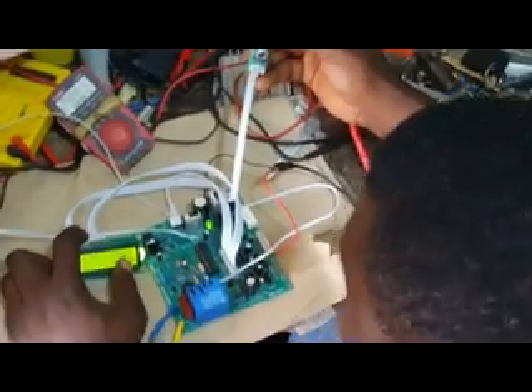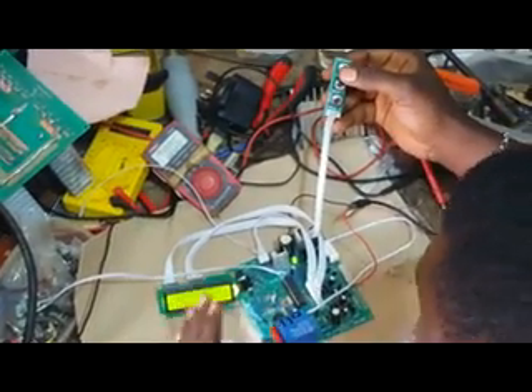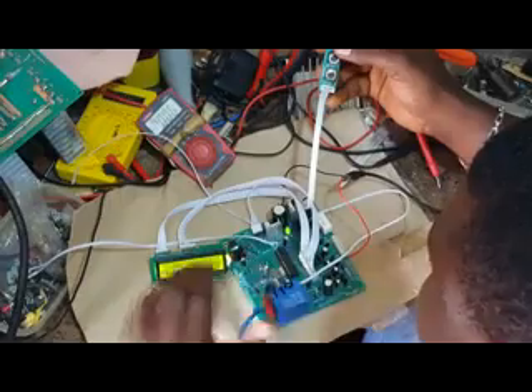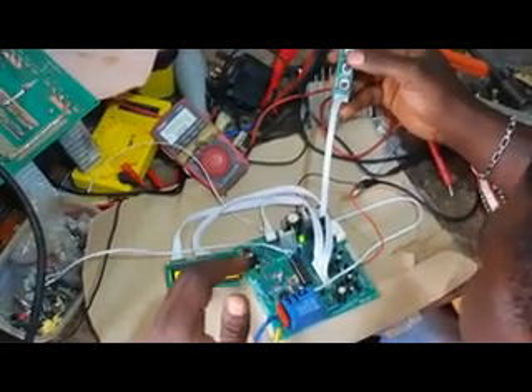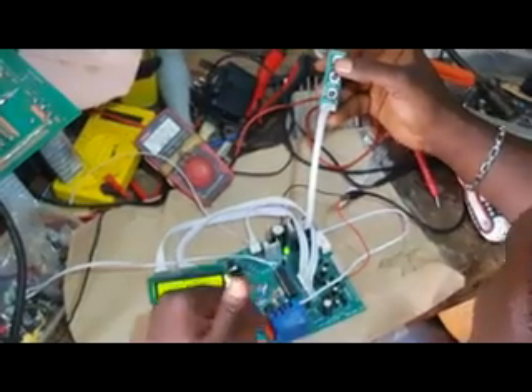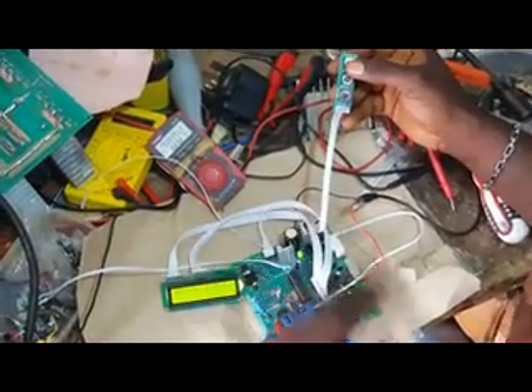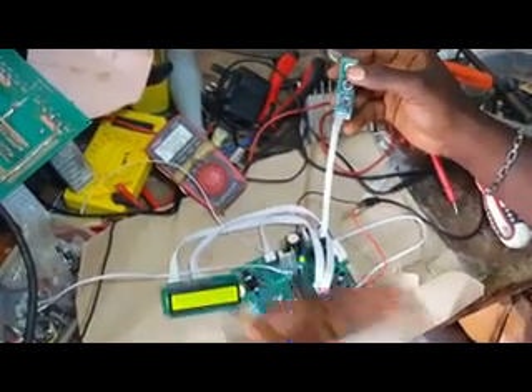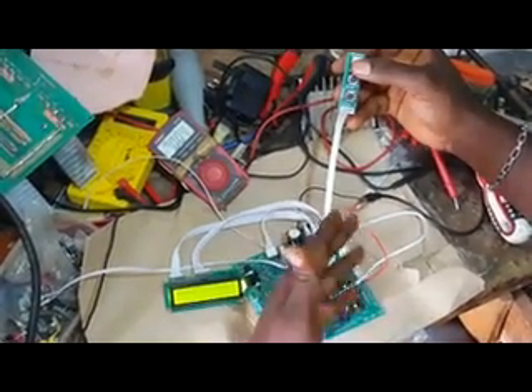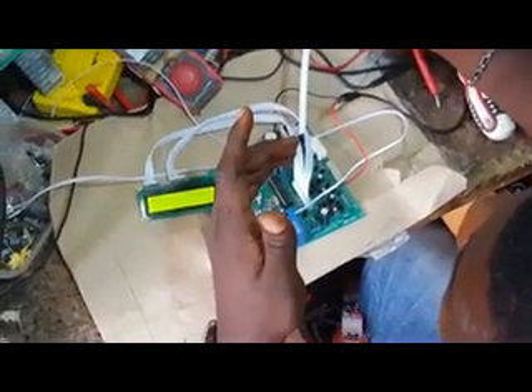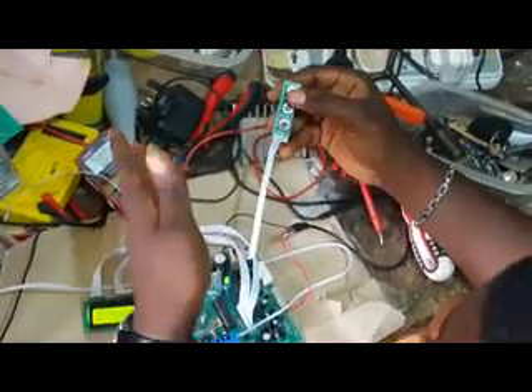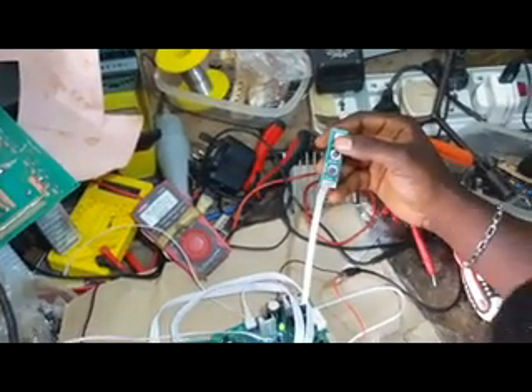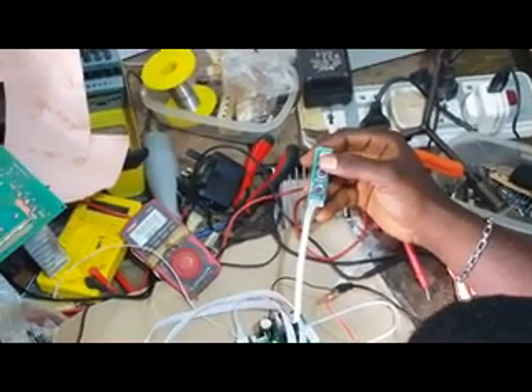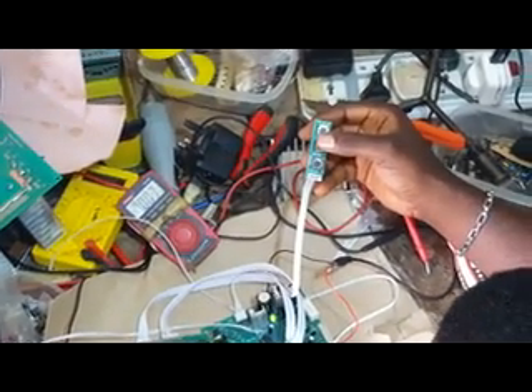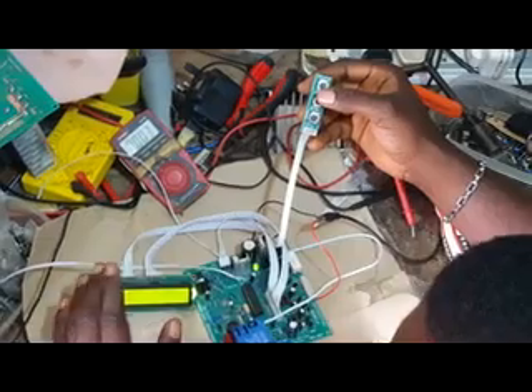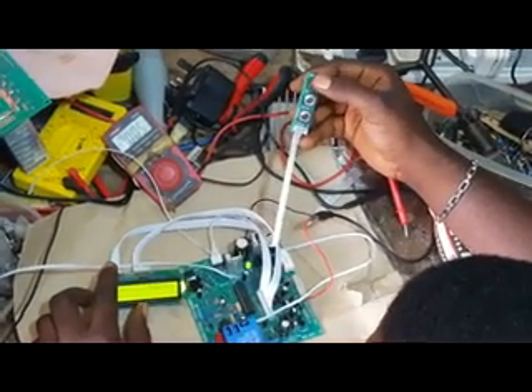That's 14.4, for a 12 volt configuration. Keep in mind, whatever you're designing, if it's for 12 volts, follow 12 volt values. For instance, a 12 volt battery should cut off at 14.6 or 14.7, depending on how you want it. For a 24 volt system, you'd double that value - there shouldn't be a mistake in this area. So for the 12 volt design I'm doing now, 14.4 is still enough for the battery to cut off, but I'm going to increase this to 14.6.